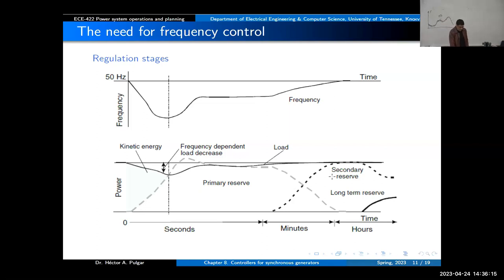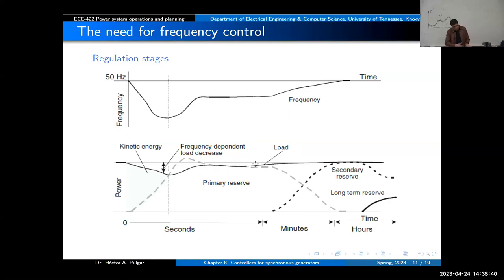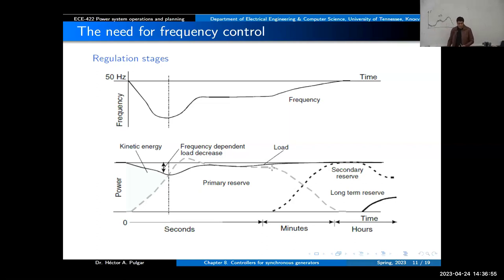When you use the primary reserve to increase power to cope with frequency deviation, at some point the frequency will be stabilized using that reserve. But then later, maybe in the scale of 30 minutes or more, you have a secondary reserve. Maybe you need to start up a power plant that was off — not committed in the unit commitment — or you have other devices that need more time to prepare and finally produce that extra power. Eventually that power becomes available, it's injected into the system, and the frequency can be restored back to 50 hertz.